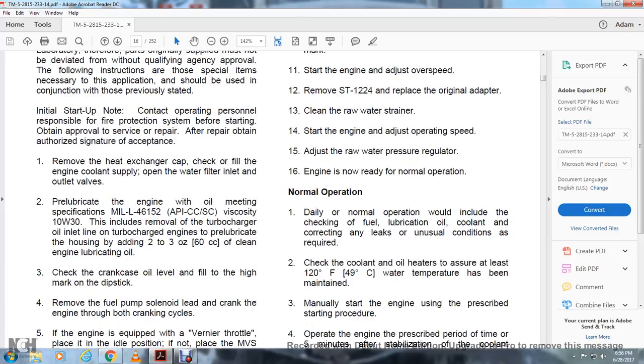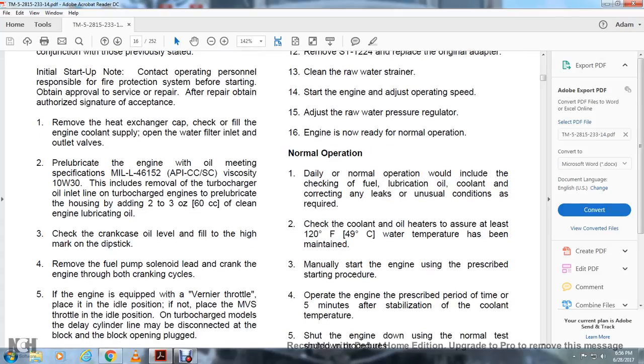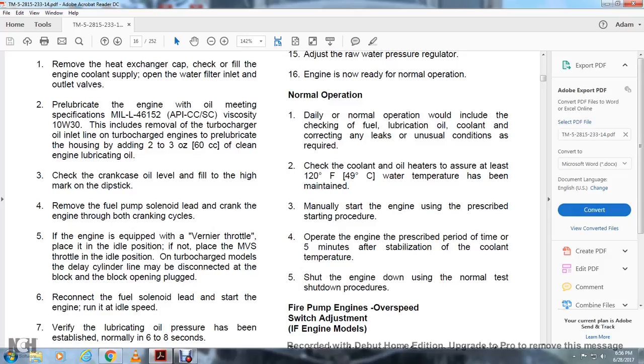Normal operation would include checking the fuel, lubricating oil, and coolant, and correcting any leaks or unusual conditions as required. Check the coolant and oil heaters to ensure that a water temperature of at least 120 degrees Fahrenheit has been maintained. Manually start the engine using the prescribed starting procedure. Operate the engine for the prescribed period of time, 5 minutes after the coolant temperature stabilizes. To shut the engine down, use the normal test shutdown procedures.